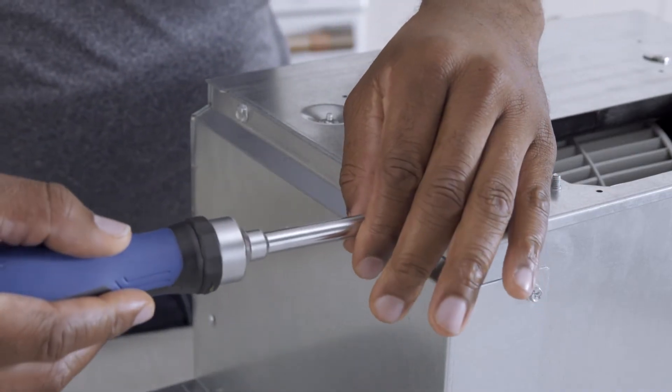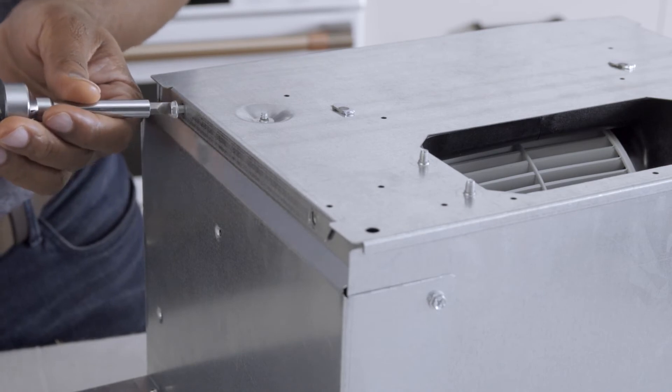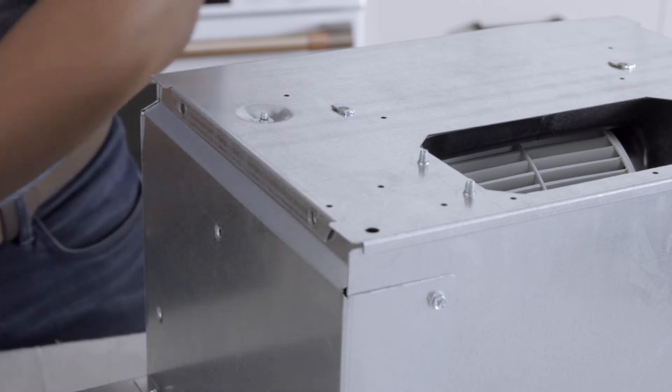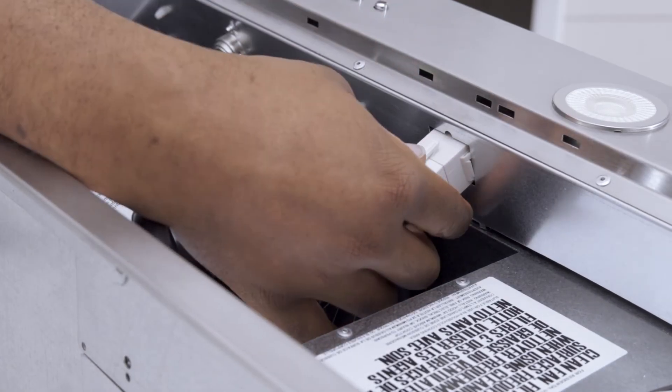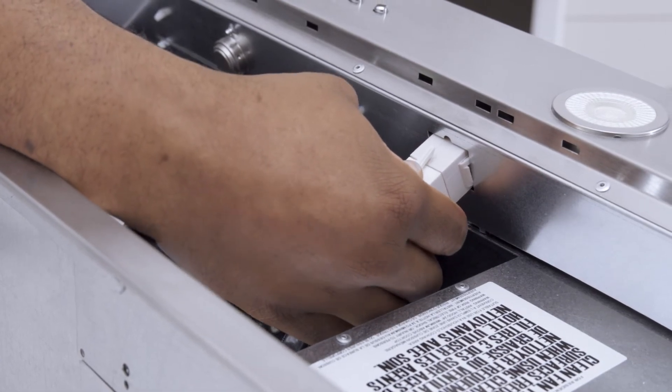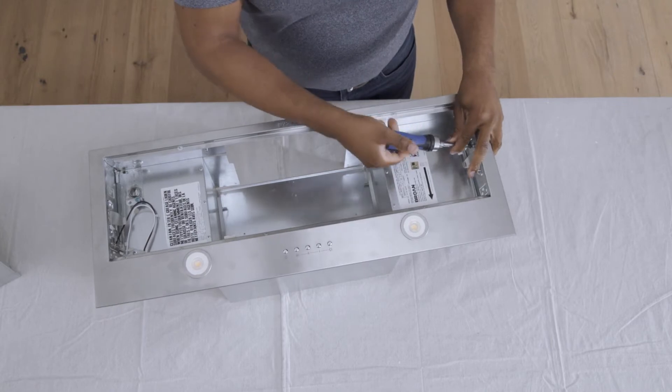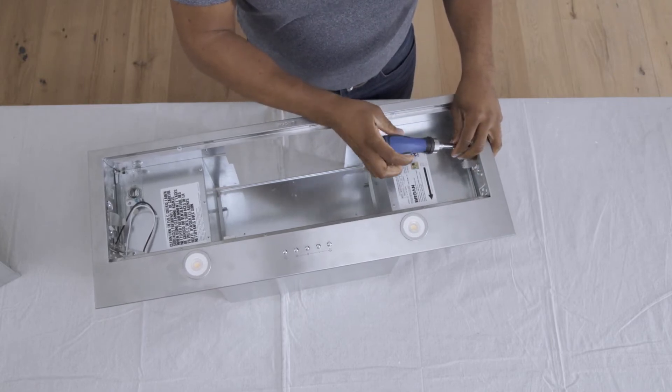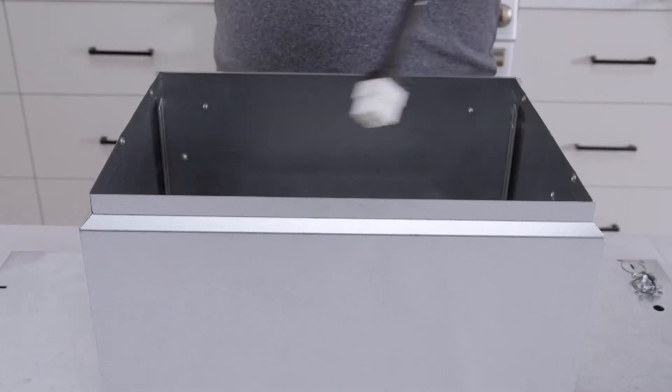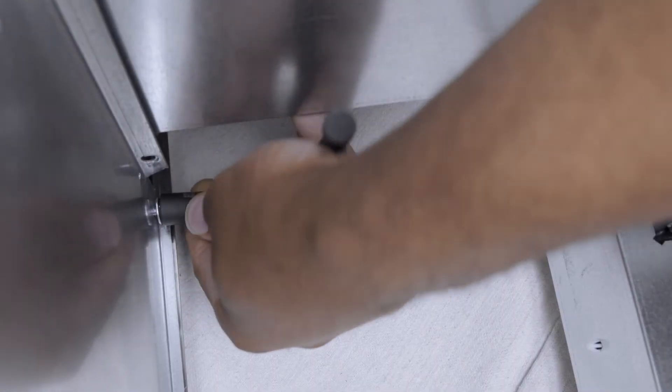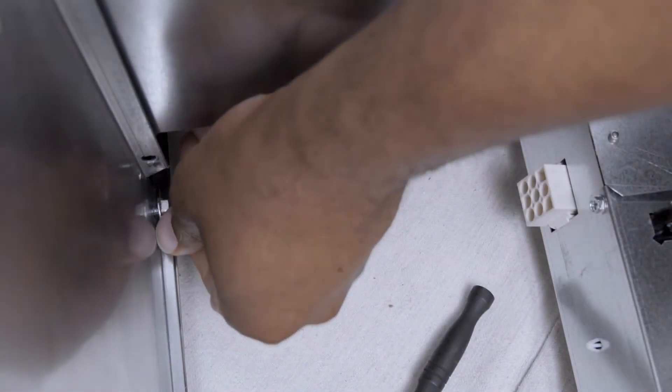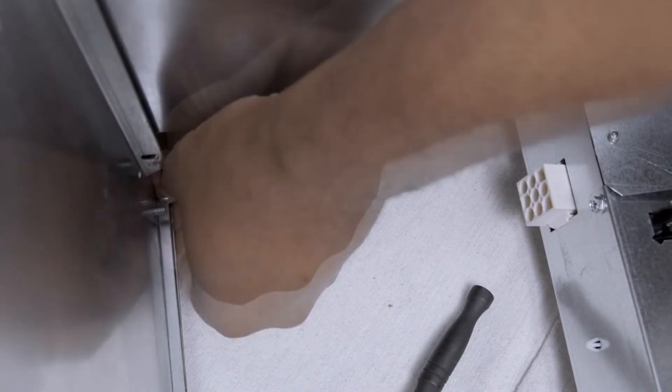To switch the unit to the optional horizontal exhaust, remove the four retaining screws from the faceplate. Then, unplug the blower cable from its connector on the faceplate. Remove the four screws from the support plate on the top of the unit. The blower will be reinstalled later. Detach the backplate by removing both retaining nuts using a 3/8 inch socket.